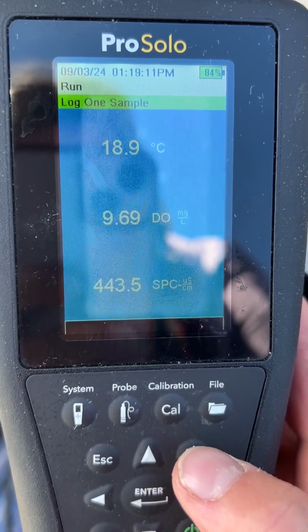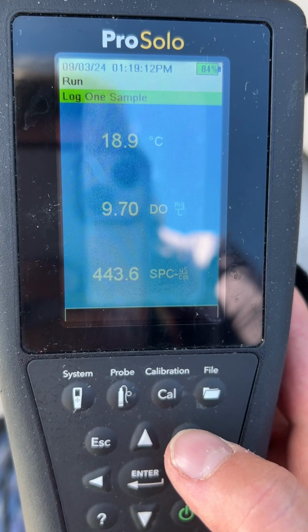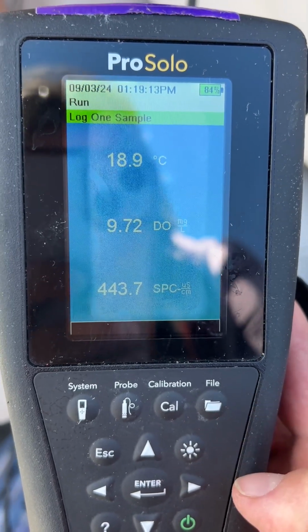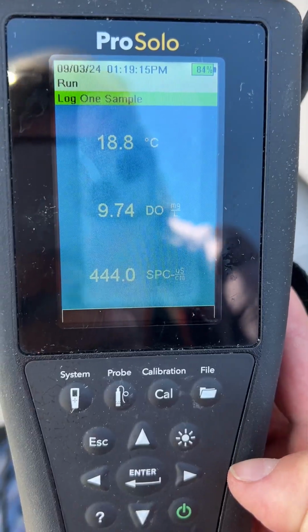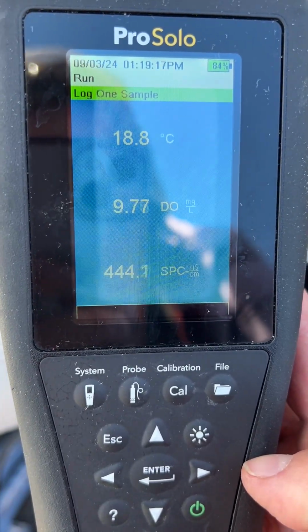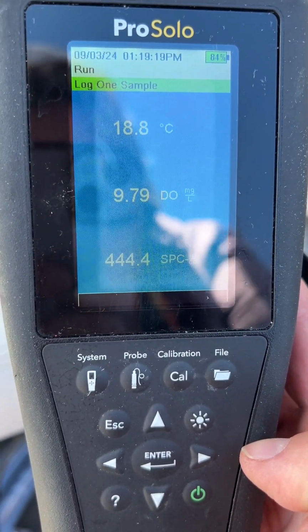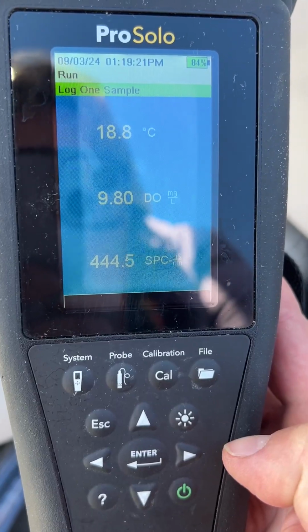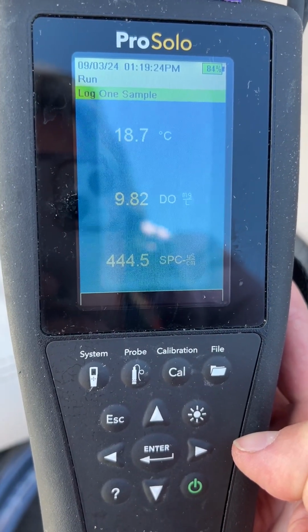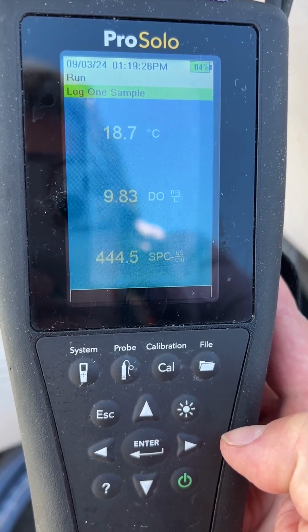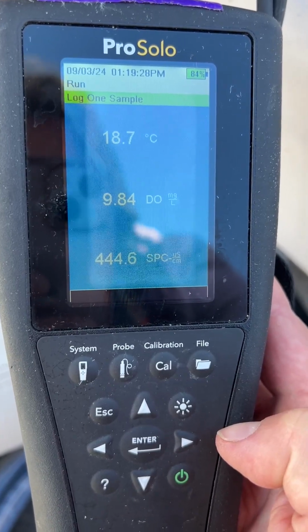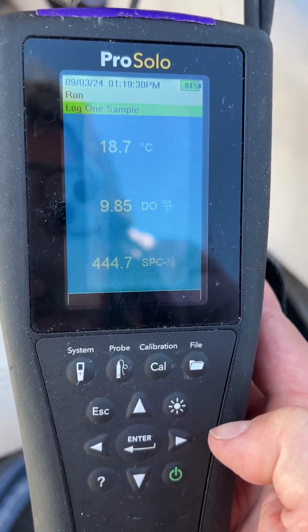When you first put it in the water, wait a couple minutes for the values to stabilize and stop rapidly changing. It's likely the DO will never stop moving completely, so wait till it has slowed down significantly and use your judgment to record the reading on your field sheet. Once your numbers have stabilized, we can jot down the values that we are reading at that point.